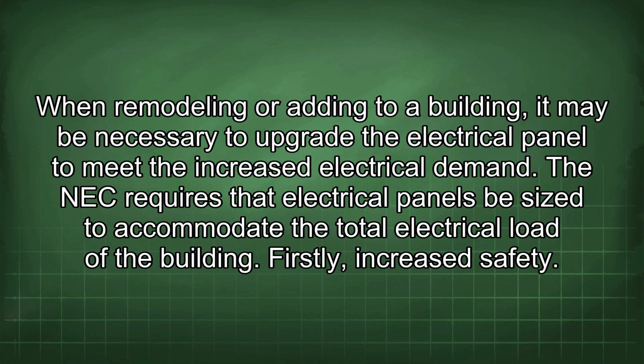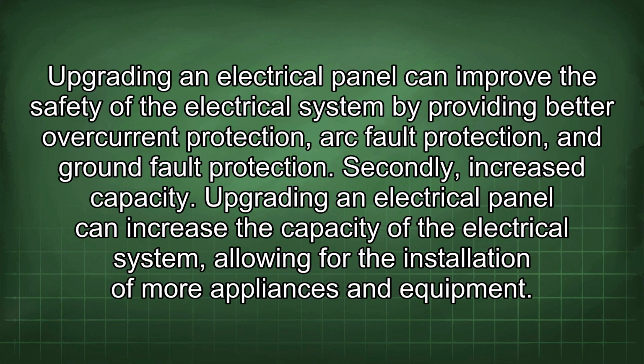Firstly, increased safety. Upgrading an electrical panel can improve the safety of the electrical system by providing better overcurrent protection, arc fault protection, and ground fault protection. Secondly, increased capacity. Upgrading an electrical panel can increase the capacity of the electrical system, allowing for the installation of more appliances and equipment.